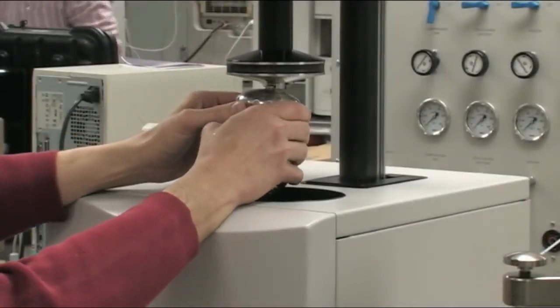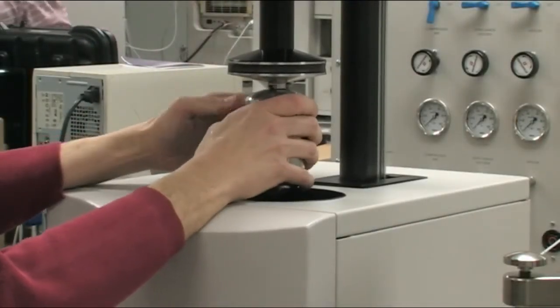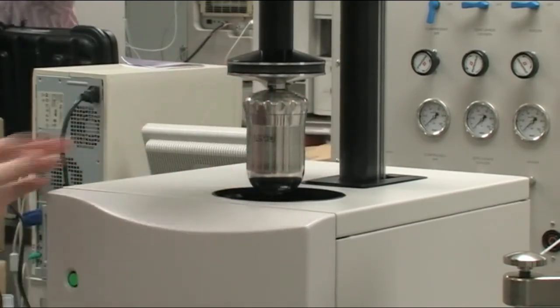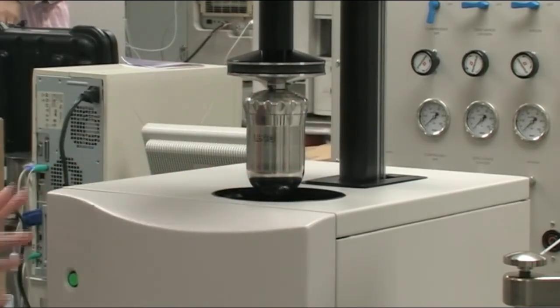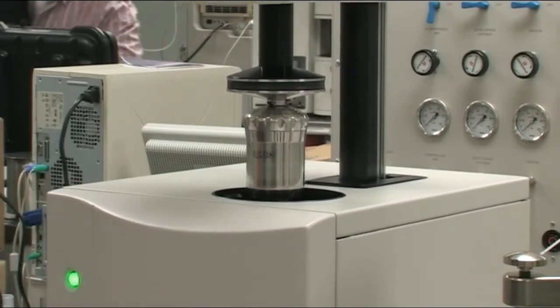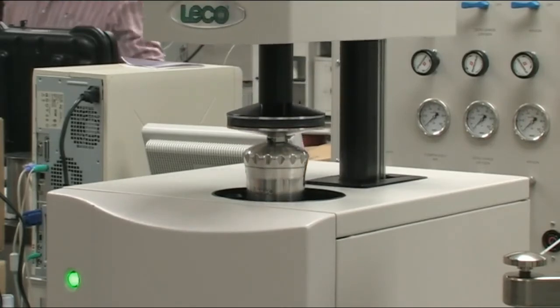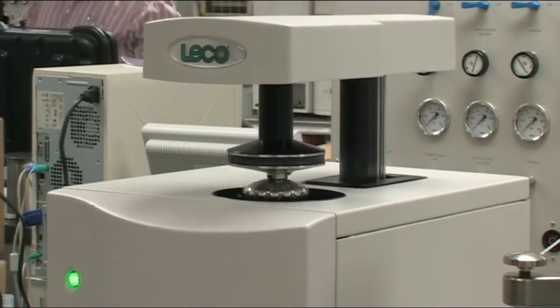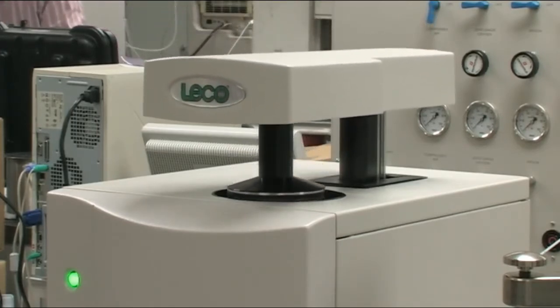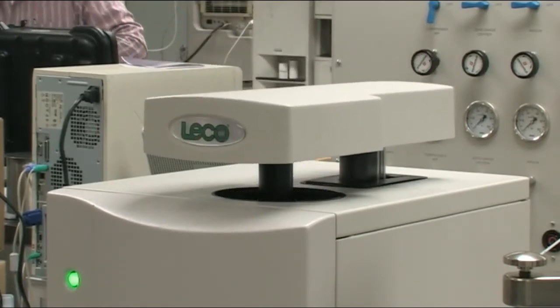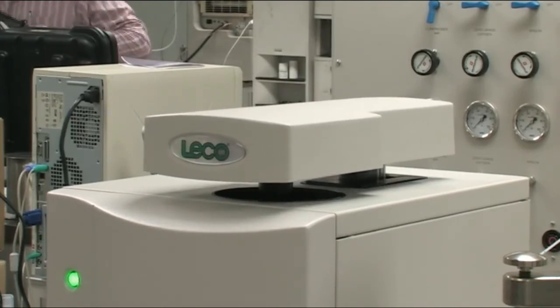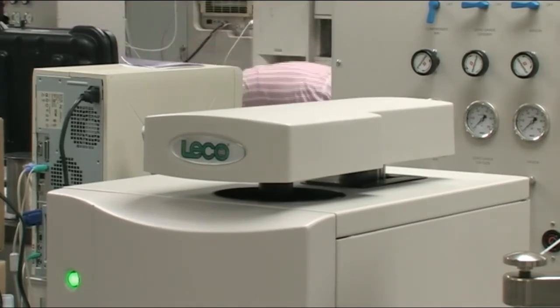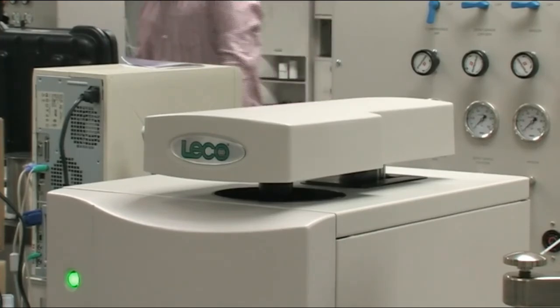We can now place the vessel onto the load head, slide back, and let it hang freely. Make sure you slide the vessel all the way back. You then want to press once the green button on the instrument. What it's going to do now, it's going to lower the vessel in to a certain point and do a check on temperatures. Then it's going to lower it the rest of the way, inflate the bladder to seal the bucket, and we'll do the ignition and fire the sample. The equilibration time for this is approximately 70 to 80 seconds. Then it will ignite the string to ignite the sample and run the analysis.